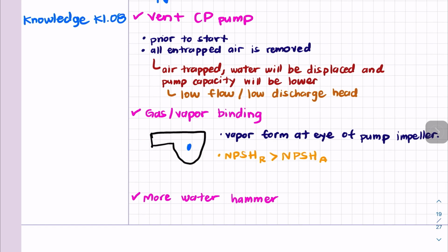Also, it is important that we select a good pump for the application that we are looking for, and we need to make sure that we have a sufficient net positive suction head value. But it's also important to install a suction strainer or another device to prevent this gas or vapor from entering the pump. And obviously, regular maintenance and inspection of the pump can also prevent this. Also, identify potential issues and take corrective action as needed as well.